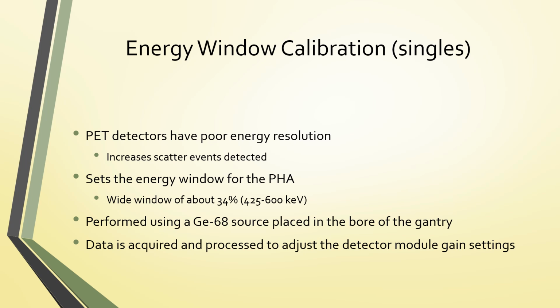Now for the energy window calibrations, also known as singles, the PET detectors just naturally have poor energy resolution. This increases scatter events that are detected. It's got a wide window, typically of about 34%. So even though it's centered on 511 keV, it's going to accept anything between 425 and 600 keV, which means that especially down closer to the 425, 450 keV, you're going to end up accepting a lot of scatter.